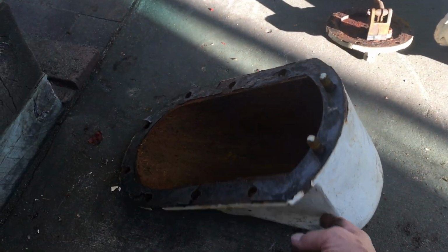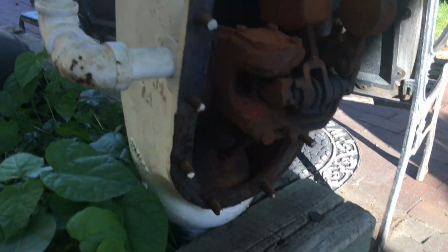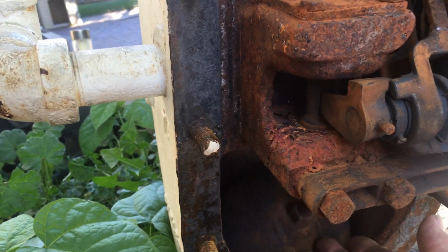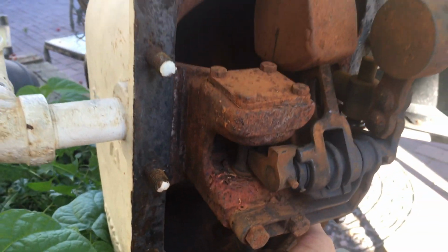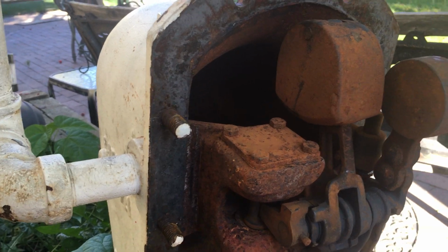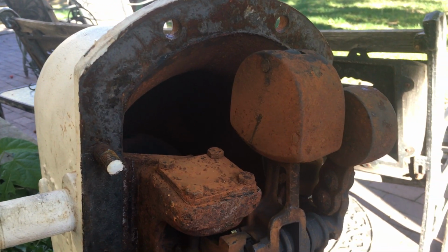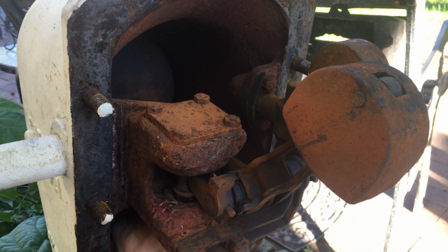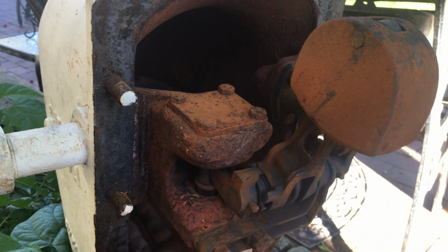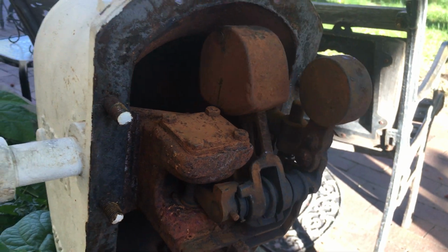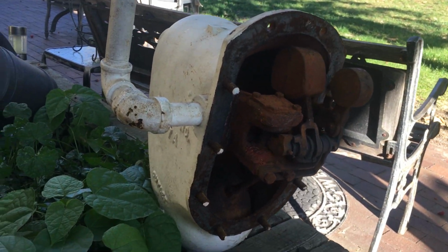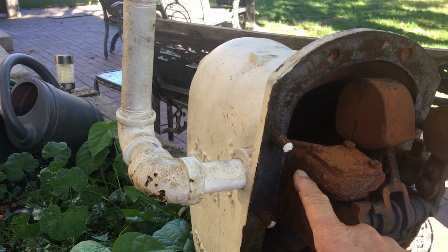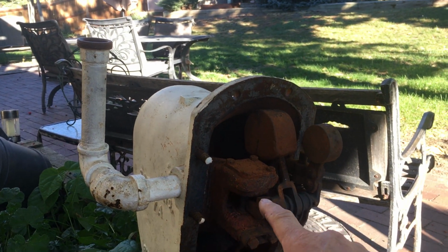This cover is the one that's covering the front of this. And there's a float in here, right there. As the water level rises, and watch what happens, there's a counterweight that trips and holds the valve open, and then as the float drops, it trips closed. So you have steam coming in here to a valve, and the valve is normally closed.